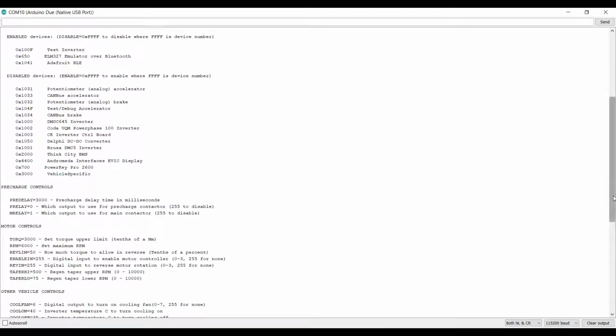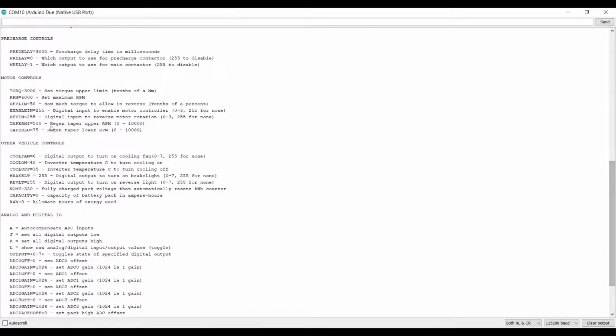But the important thing we want to look at are these three numbers right here, the precharge controls. The precharge relay delay is set to 3000 milliseconds, or 3 seconds. The precharge relay control output pin is pin 0, and the main relay control pin is pin 1. So that is the way the GEVCU has been wired.